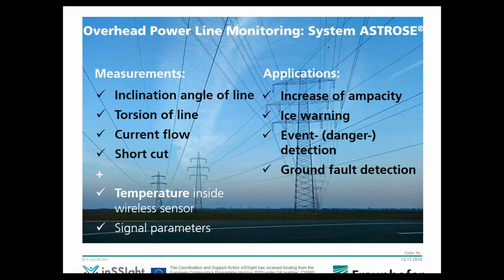We would like to present the system Astrose, built for overhead power line monitoring. In this webinar we want to show that we had to build a very robust wireless system, and the measurement task is at least measuring the inclination angle of the line, which is used to measure the sag of the line, since that's a key parameter for the ampacity of the power line.